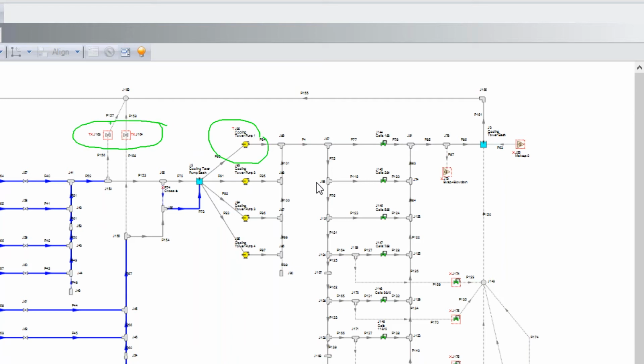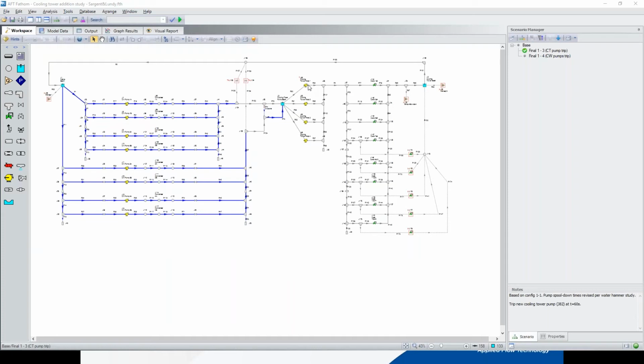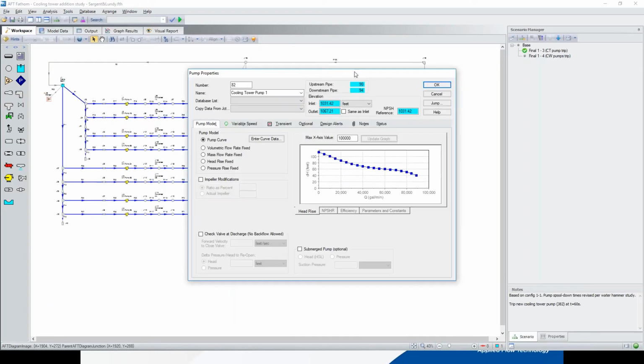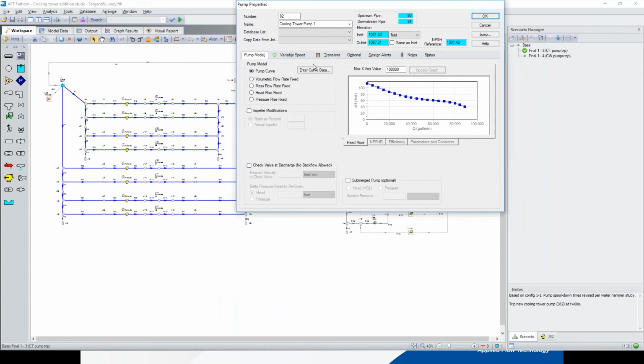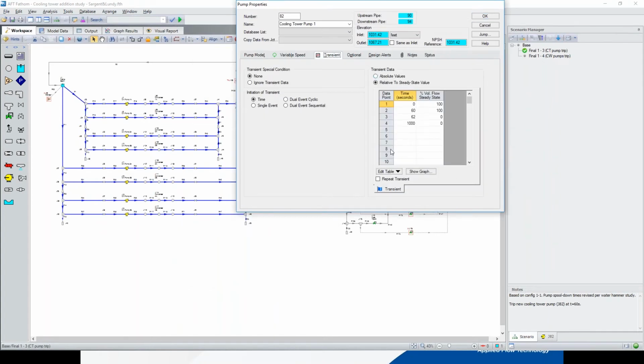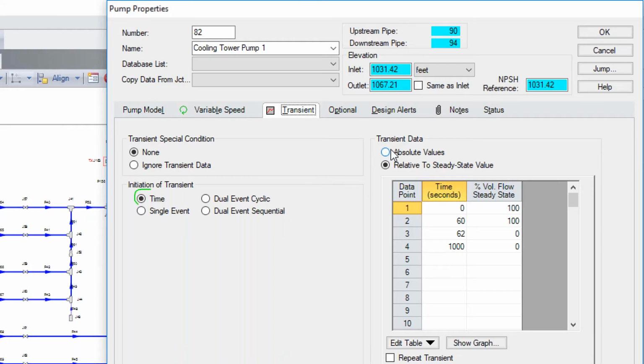The first step when you use XTS is you go to analysis and you say time simulation, and you activate it for a transient. Then you have to set the transient events. Here we have 2 transient events. We're tripping this pump, and we're opening this valve to recirculate the water to the old tower. So let's take a look at the trip of the pump.